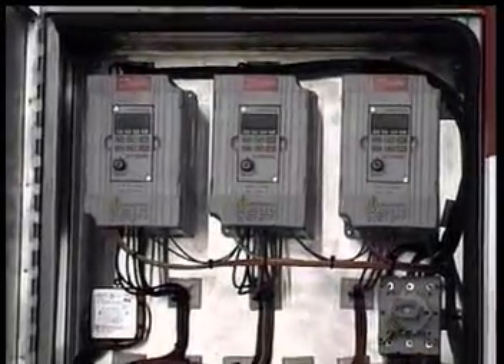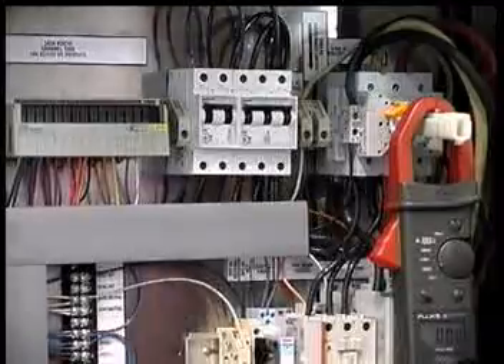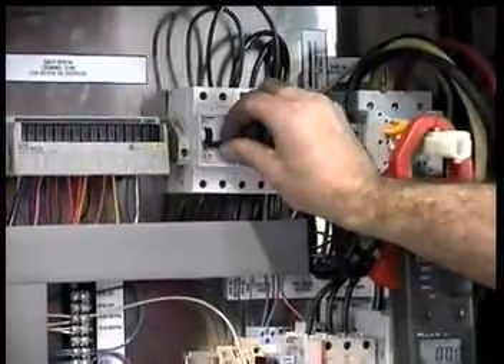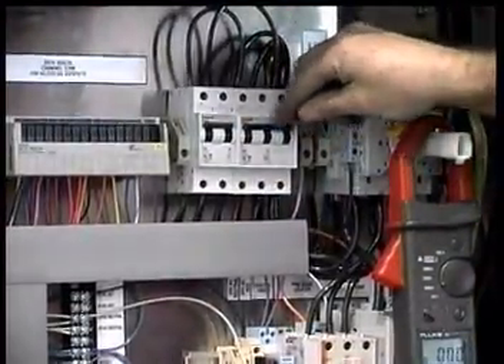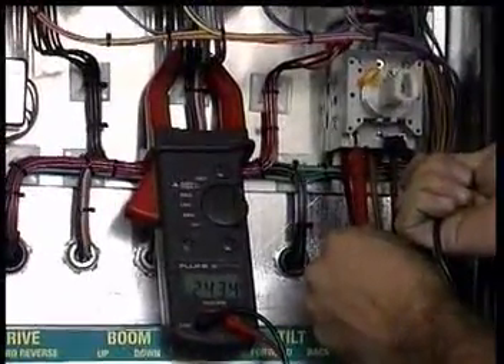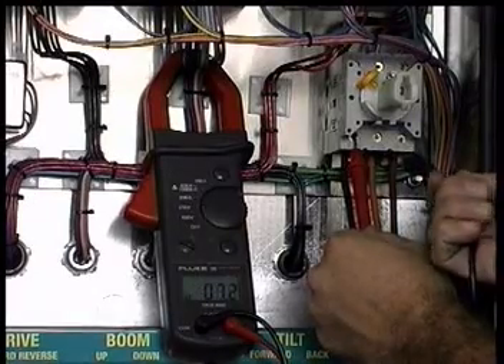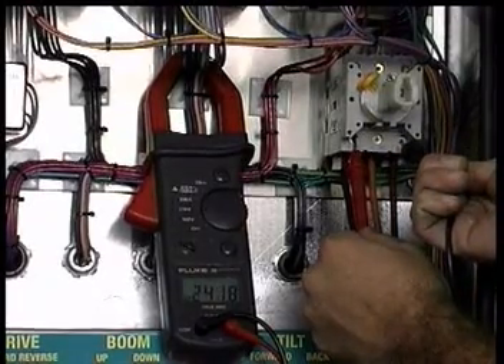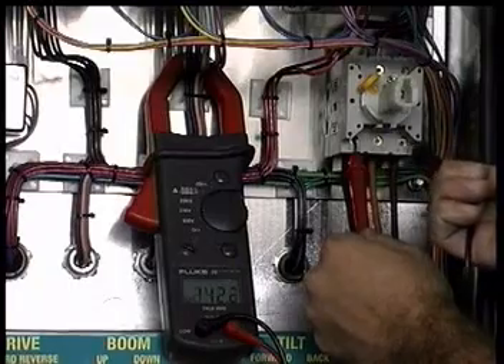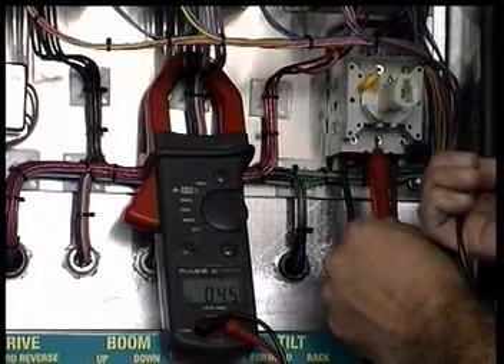If the Danfoss motor drives have lost power, begin by checking the breaker in the control panel. If the breaker is not tripped, use a voltmeter to check for voltage at the gantry control panel disconnect. Checking voltage instructions are in Chapter 13. Then check wiring from terminal strip to drives.